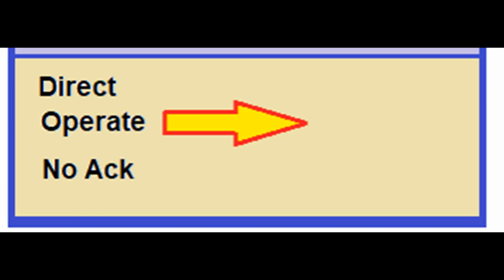Something that may concern you is that some outstations may accept a broadcast request with the direct operate no ACK function code. For example, a master may be able to send a single message to control point index 1 at all outstations. It used to be a requirement that outstations support this capability. It is not so certain anymore whether this is still a requirement.